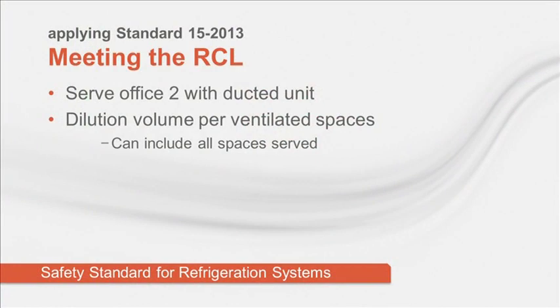For our example building, a good way to increase dilution volume is to use a ducted VRF unit to serve Office 2 and another room. For ducted units, dilution volume is determined by the ventilated spaces section of Standard 15. As mentioned earlier, this allows all spaces served by the unit to be included in the dilution volume. Meeting the RCL requirement outlined by Standard 15 might be more difficult for VRF systems, but it certainly isn't a showstopper.